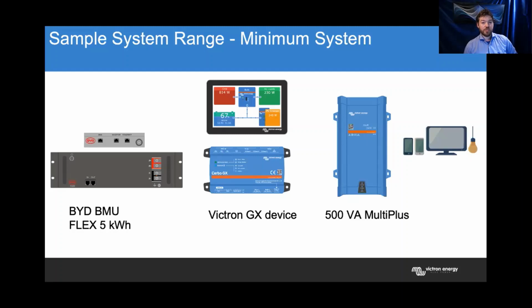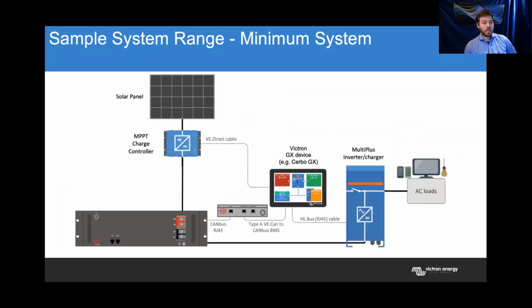This is an integratable system. You can see here some of the functional lines connecting a system like this together. So we've got the MPPT charge controller connected to our Cerbo GX with a VE.Direct cable, or a VE.Can cable if it's a VE.Can MPPT. The battery itself is also connected to the Cerbo GX via its BMU, and then the inverter charger needs to be connected via the VE.Bus cable.